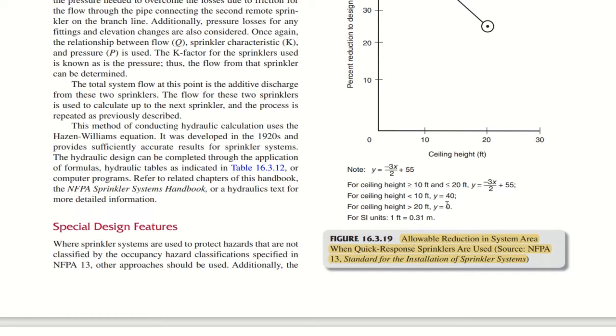So based on the ceiling height, the percentage reduction they have shown here. If the ceiling height is more than 20 feet, then there will not be any reduction in the area. So you just consider 1500 square feet area of sprinkler operation.